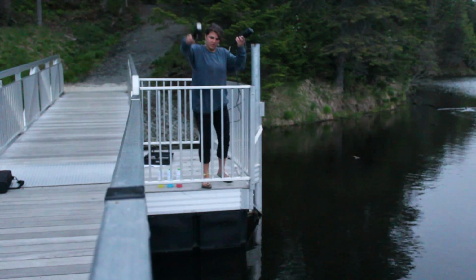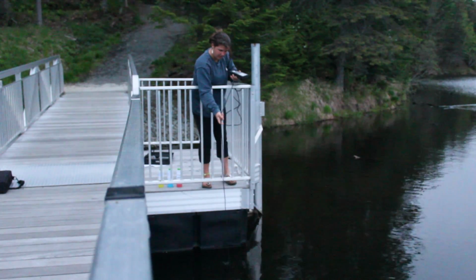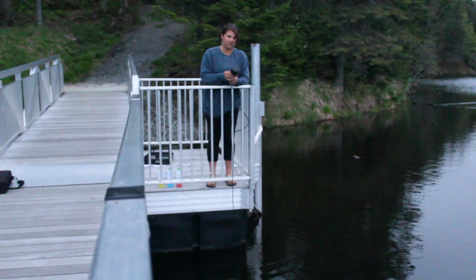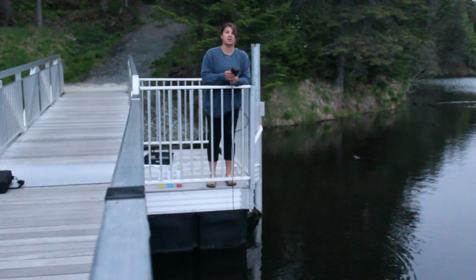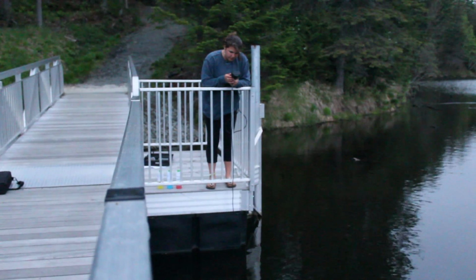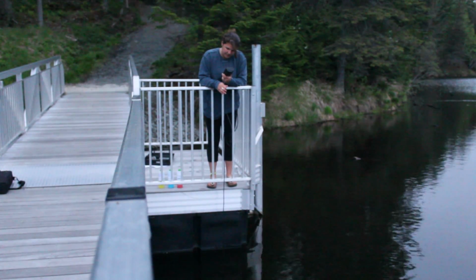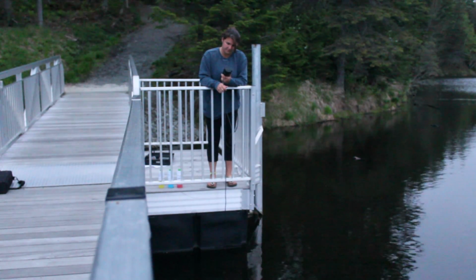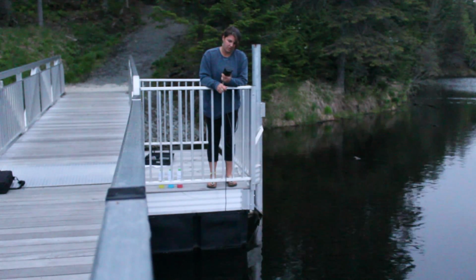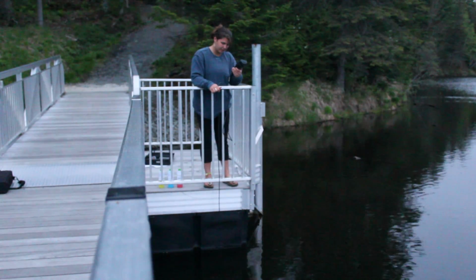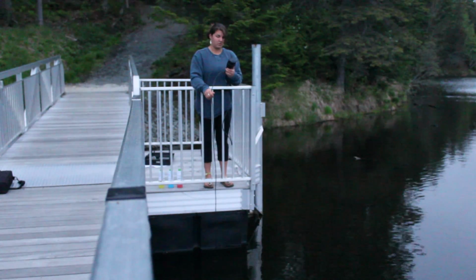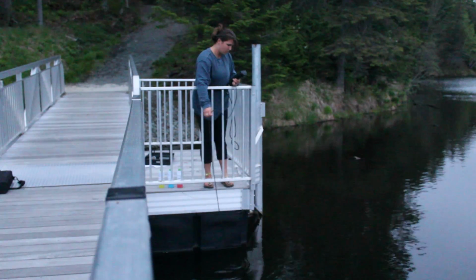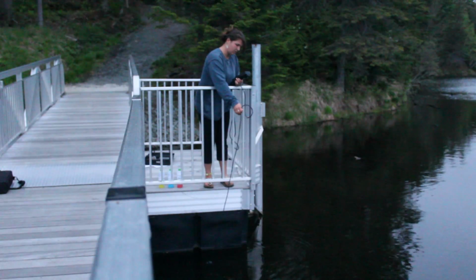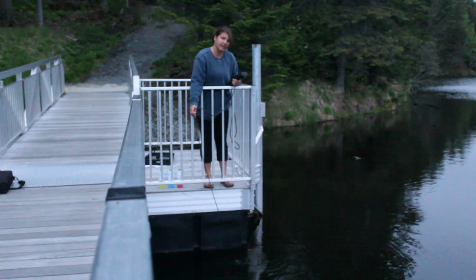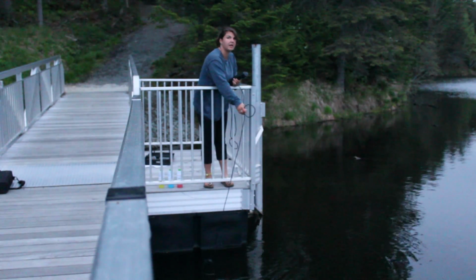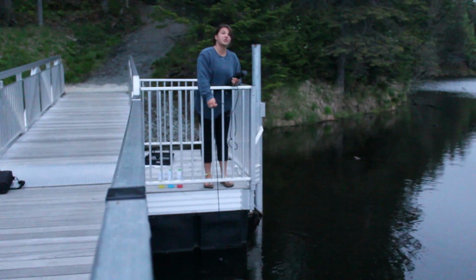So we're going to dip it in the water slowly. And we're going to read our readings, and it gives us our dissolved oxygen in milligrams per liter, and it gives us specific conductivity in milliSiemens per centimeter, and it gives us conductivity in milliSiemens per centimeter, and it gives us our total dissolved solids in milligrams per liter, and our salinity, and it gives us our pH and chlorine in milligrams per liter too. And this machine needs to be turned on for at least 10 minutes to warm up. So it should give us our reading, and since we have a dissolved oxygen, we're going to slowly rock it back and forth, and it should give us our readings in time. So you've got to give it time to settle in, and once all the values are at a constant number, then you can read them off. It's not working right now, but it should lock in.